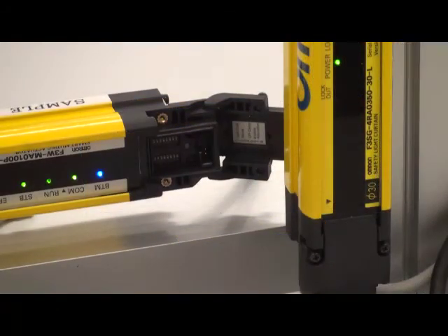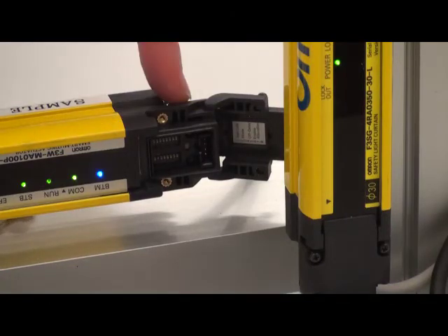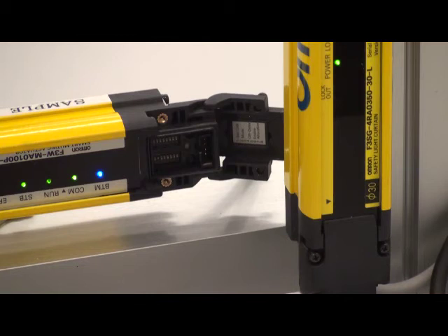And now I want to show where the dip switches are located on the smart muting actuator, which is right here, which is where we're zoomed in. And some of the functionality on these are you can change the scan code selection, which is the modulation frequency of the emitter. The operation mode, which will do anti-chattering, which we're going to discuss in the next video.